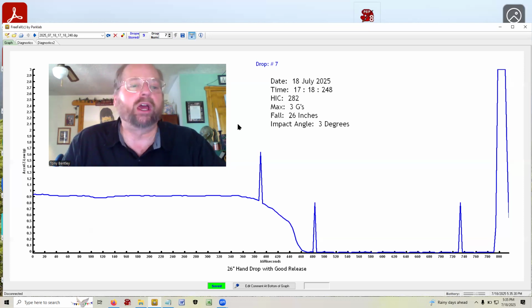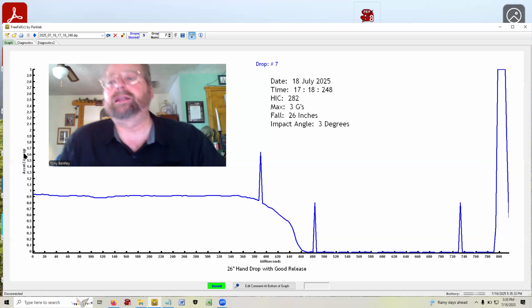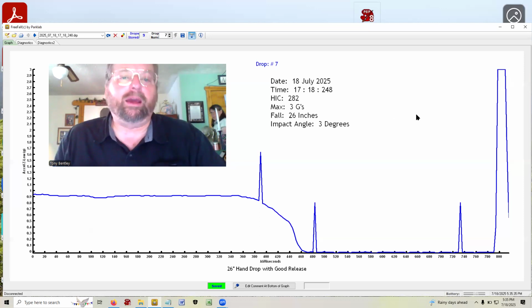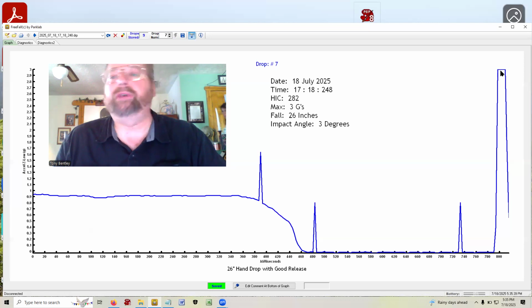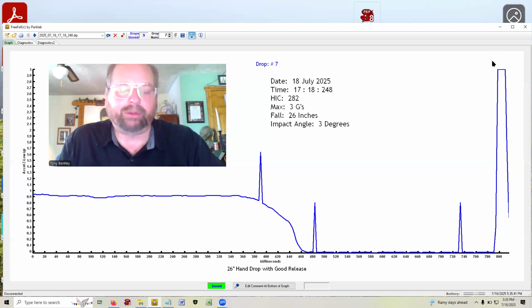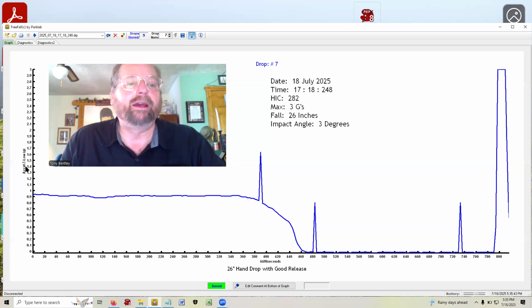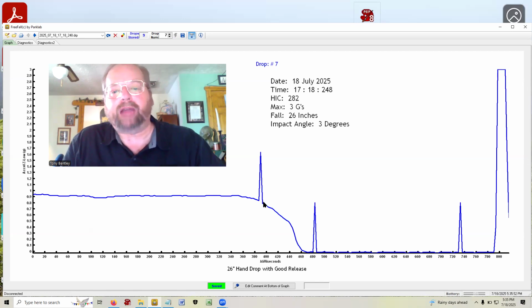Now, since this is the low Z accelerometer, it doesn't measure the full impact. This one saturates here at 3 G in this case. It doesn't go up to the 200, but the high accelerometer for the z-axis does. But this is what's used to calculate the fall height. Now let me explain. So this is the actual data.